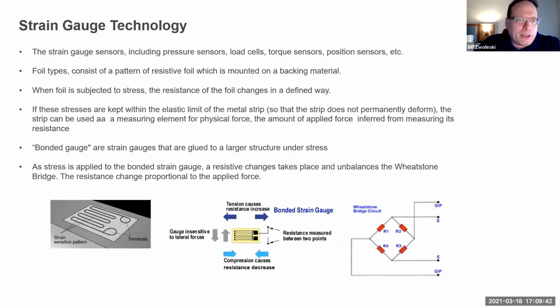Strain gauge technology: we talk to a lot of engineers and scientists who are very intimate with it. This basically uses a Wheatstone bridge, where the change in resistance is proportional to load. You work on a flexure basis, where as it flexes, it changes the resistance of the bridge, and that relates to the load. It's purely a static measurement technique. However, it does have some dynamic capabilities depending, but it's probably known most for its low frequency characteristics.